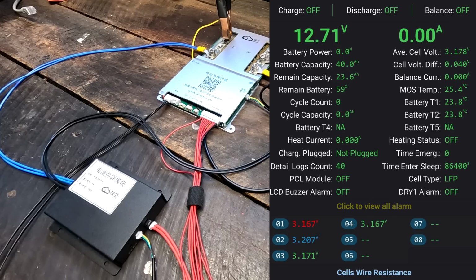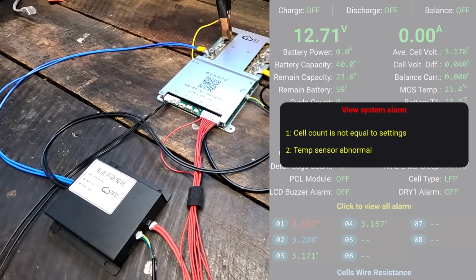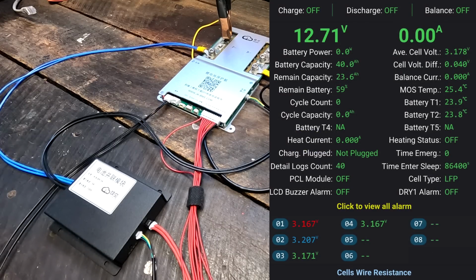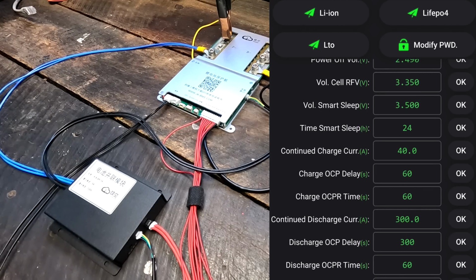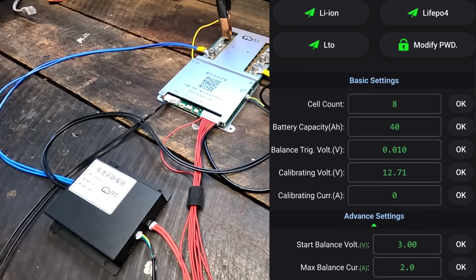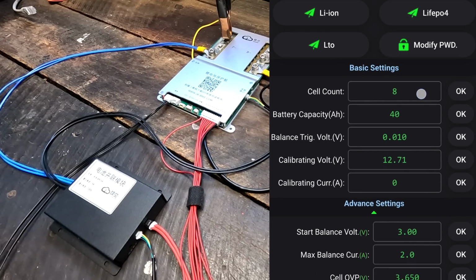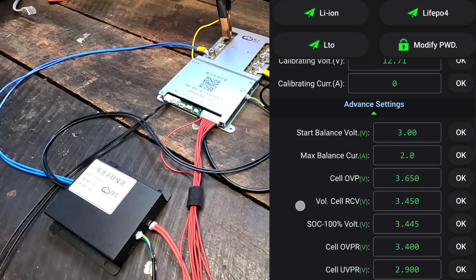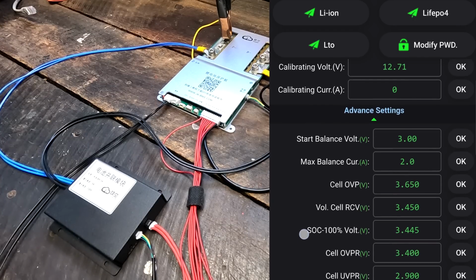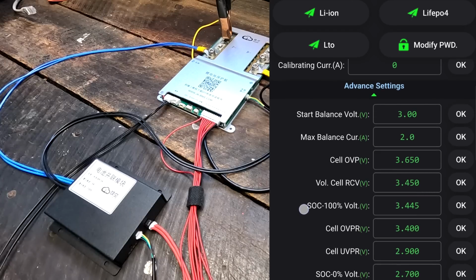Okay, so we're now logged into the app. We've still got this alarm saying cell count not equal, temperature sensor abnormal, that's fine, we'll fix this in a second. We've got all 4 cells down here at 12.7 volts. Going to settings, the first thing we want to do is click the lithium iron phosphate button up here to reset everything. Then cell count is 4 cells, capacity 105 ampere hours, not that it matters here. And we have a quick look through all the settings, because this is the default settings the BMS comes with.